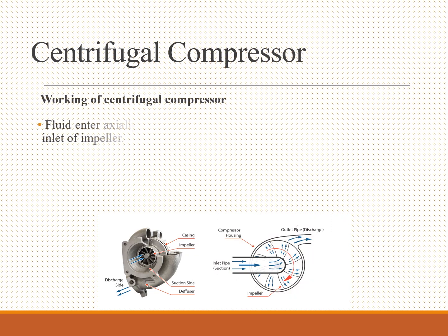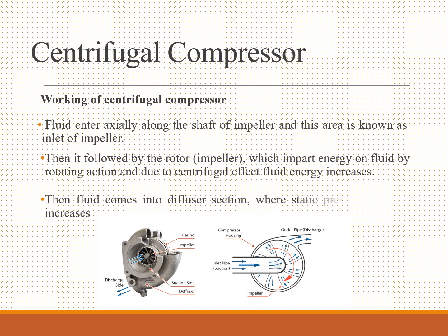So now we discuss the centrifugal compressor. What is the working of a centrifugal compressor? The fluid enters axially along the shaft of the impeller, and this area is known as the inlet of the impeller. Then it is followed by the rotor, the impeller, which imparts energy to the fluid by rotating action, and due to the centrifugal effect, fluid energy increases. Then the fluid comes into the diffuser section, where the static pressure of the fluid increases.